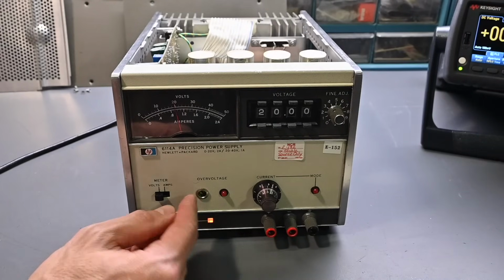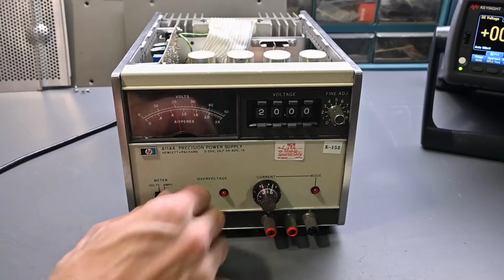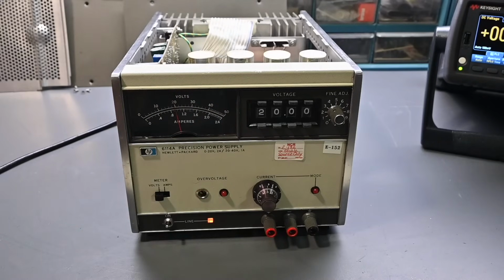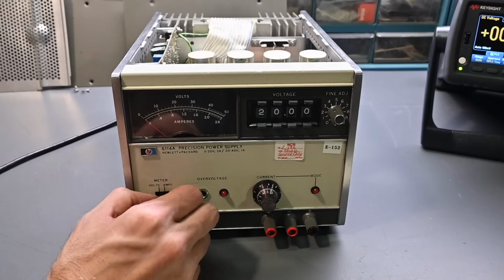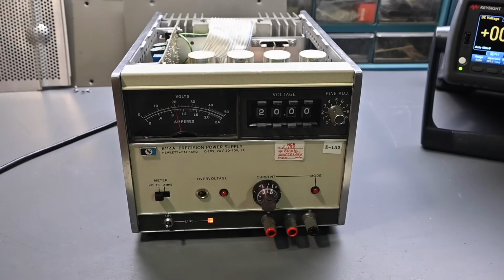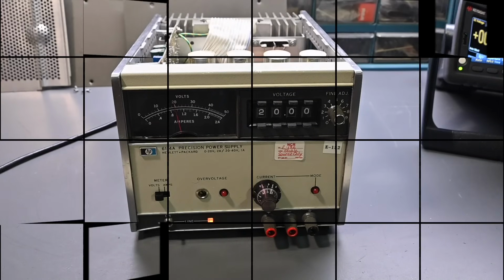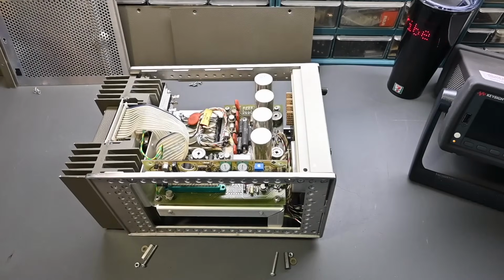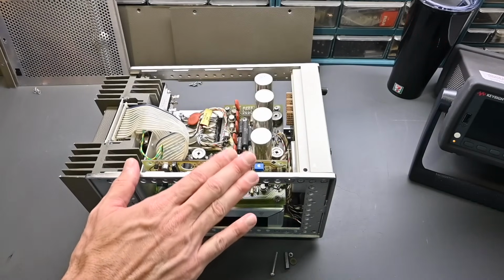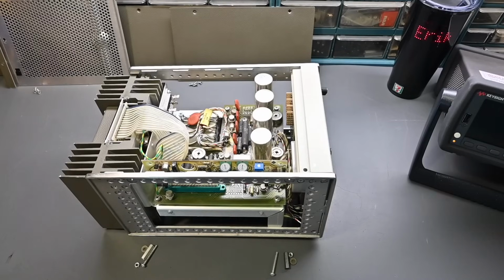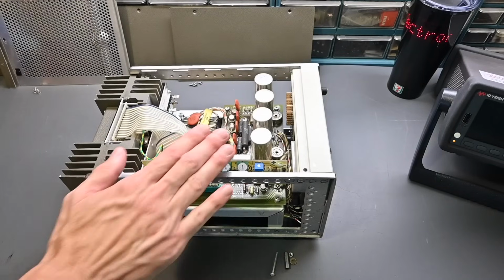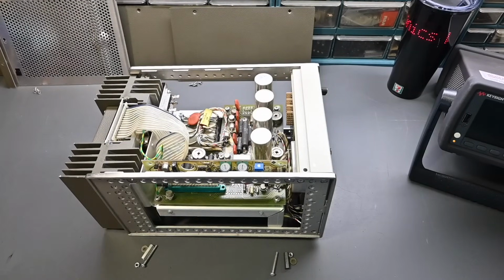To clean that potentiometer, I just sprayed that cleaner in there, worked it back and forth a dozen times or so, rinsed it with some more cleaner. And basically the same with the switch, a little shot of the cleaner in there, worked it back and forth a number of times. So I cleaned inside the power supply. I used a soft anti-static brush and some compressed air, just to remove the dust on the circuit board and around inside the chassis. So everything looks very nice inside the power supply at this point.